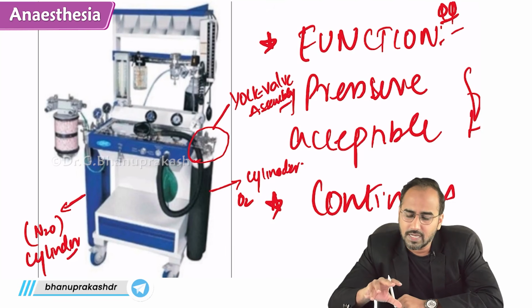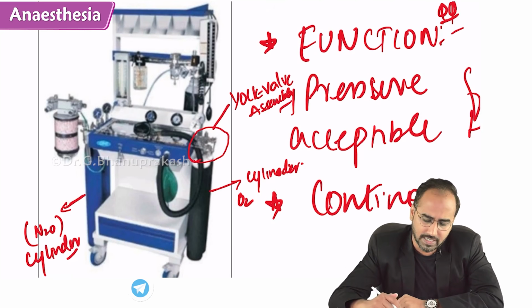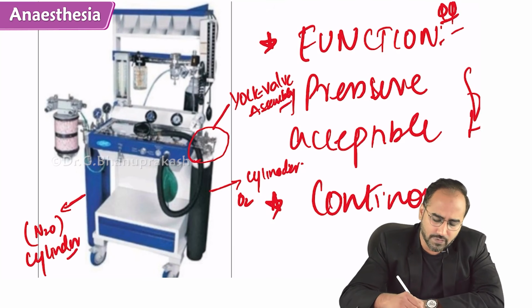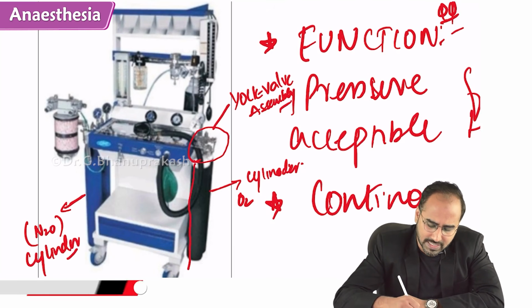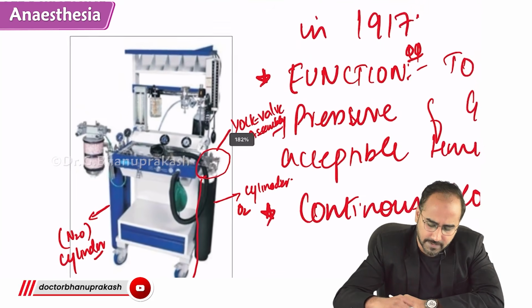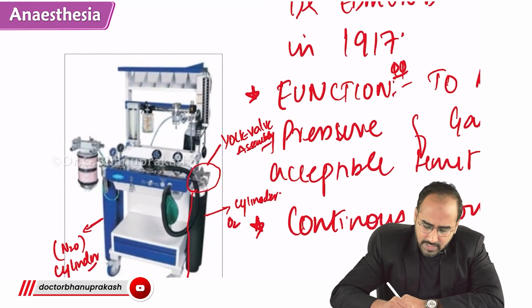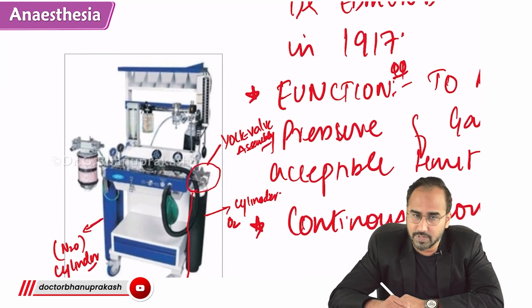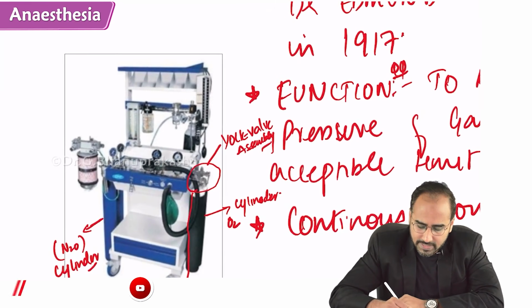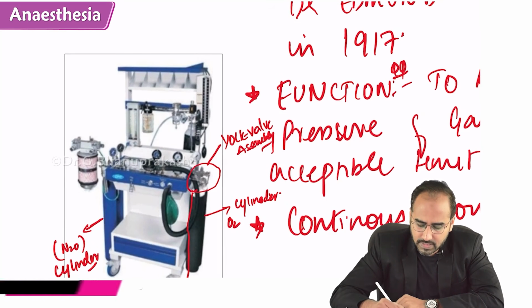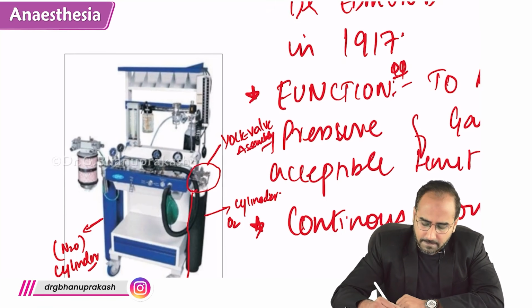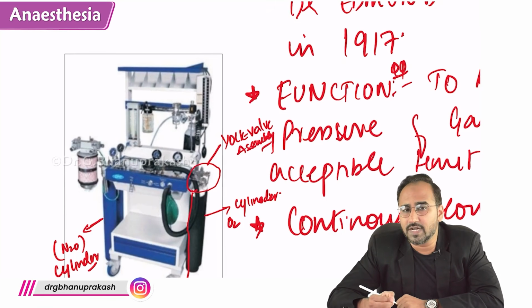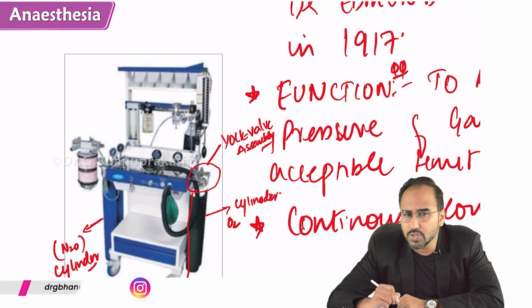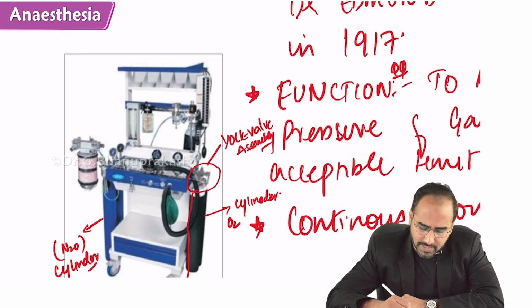Inside the yoke valve assembly, if you look at the inner surface, you will see a system that prevents the wrong attachment of the cylinder. What is that system called? That system is called the pin index system. What is the function of the pin index system? The function of the pin index system is to prevent the wrong attachment of the cylinder, right?